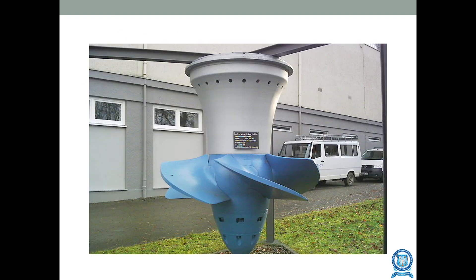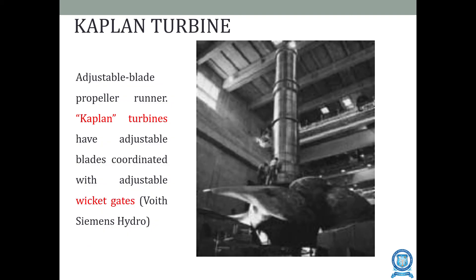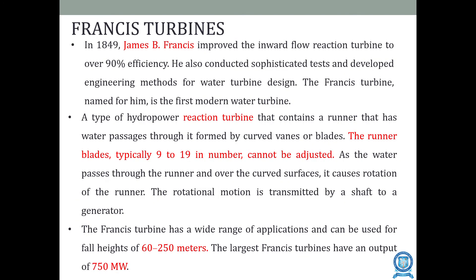Kaplan turbines have adjustable blades coordinated with adjustable wicket gates. The Francis turbine, improved by Francis to achieve 90% efficiency, is a reaction turbine with a runner having water passages formed by curved vanes or blades. The runner blades — typically 9 to 19 in number — cannot be adjusted. As water passes through the runner over the curved surfaces, it causes rotation, and the rotational motion is transmitted by a shaft to the generator.